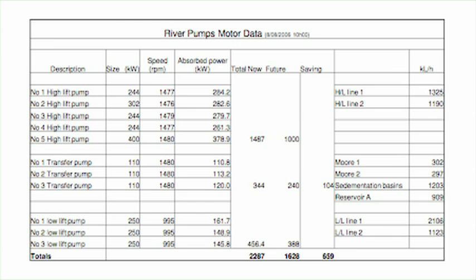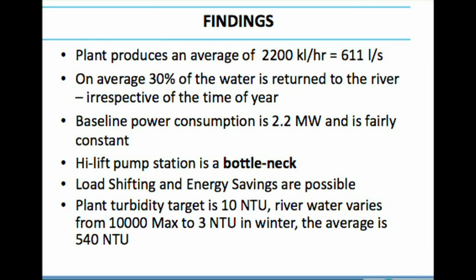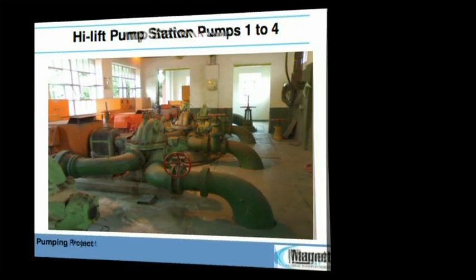This pumping section draws about 1.48 or 1.5 megawatts of power. The whole plant runs at about 2.2 megawatts. And one of the really nice things about this plant is, Gordon was talking about defining your scope and your area of analysis. It was obviously quite easy for us because we had this whole pumping station that's supplying the mill. They had already online monitoring for the power that was being used in this plant, and it was very stable at around 2.2 megawatts. That's the high lift pump station.